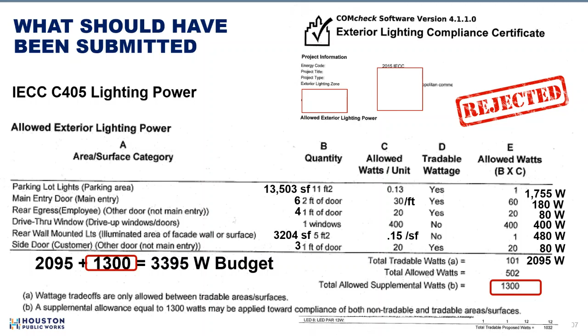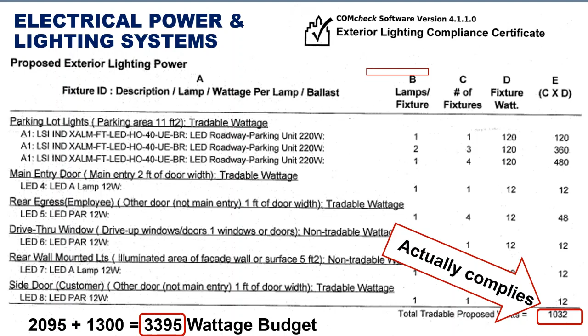And interestingly, when you look below, because this is a blow up, the total wattage of the fixtures actually complies, okay? 1,032 watts is very good, it's below the 3,395 budget. It would comply, but we are not going to allow that sort of bogus computation on a compliance certificate, okay? So a rejection note is going to be that the COMcheck was incorrectly computed for the allowed exterior lighting power component.